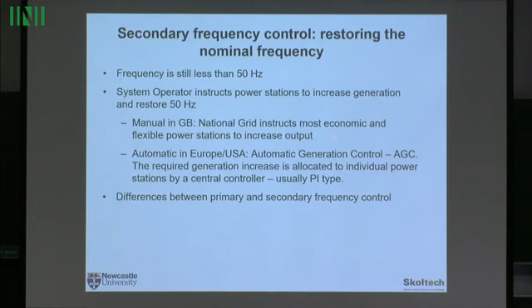So the fundamental differences between primary and secondary frequency control: primary is fully autonomous, all power stations have to contribute according to their droop characteristics, and usually similar types of power stations will have similar droop. For example, 5% for thermal generators. For nuclear generators in this country it will be less, because you don't want to mess around with nuclear power stations. With hydro, it will be more.